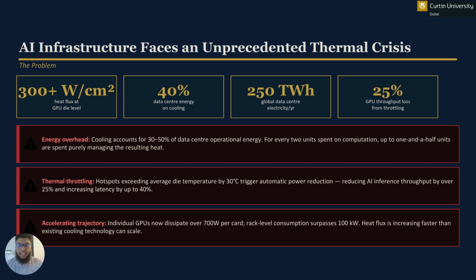The thermal challenge facing modern AI infrastructure is one of the most pressing engineering problems of our time. GPU based AI accelerators now dissipate in excess of 700 watts per card, with a rack level power consumption surpassing 100 kilowatts in leading edge deployments. Globally, data centers consume approximately 200 to 250 terawatt hours of electricity annually. Of that, 30 to 50% is allocated not to computation, but to cooling infrastructure.